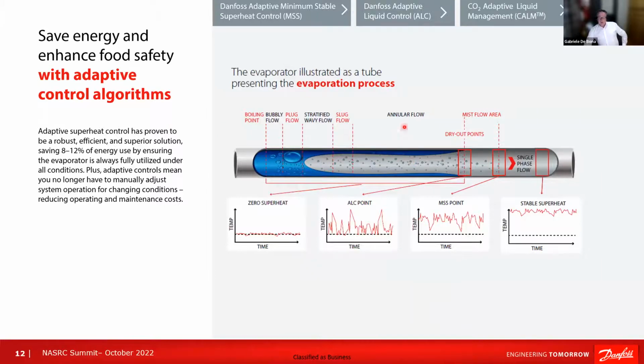Together with the ejector for CO2, we have also developed different algorithms throughout the year to manage and drive the evaporation part of the circuit. Thanks to our evaporator controller, the case controller that goes on the refrigerator cabinet, we are able with our algorithm to automatically set and keep the superheat value at the maximum performance possible.